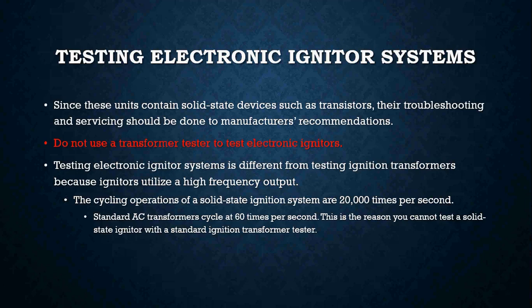Now, when it comes to testing an electronic igniter, you have to keep in the back of your mind, again, that they do not have a primary and secondary winding like the old ignition transformers, but they do have transistors and other stuff in there. So troubleshooting and servicing them should be done to manufacturer's recommendations. When you pull them out of the box, read the paper that comes along with them. It tells you how you can service and troubleshoot them. Okay, you do not use a transformer tester to test electronic igniters. They have their own separate way of doing things.